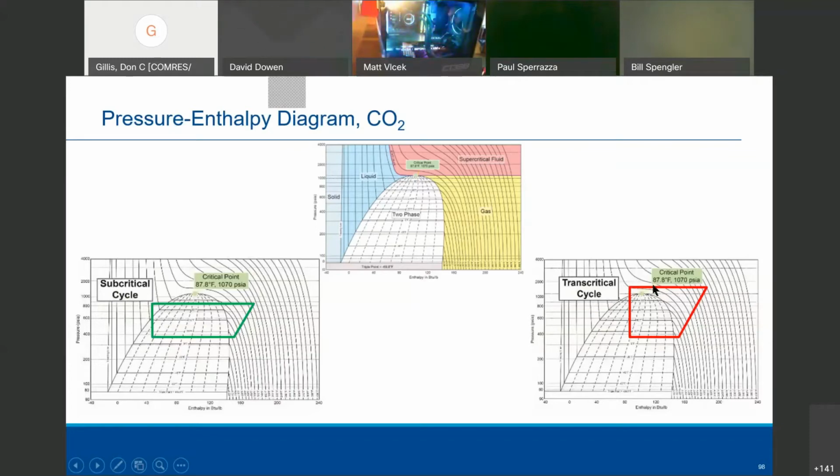When we get above that, you can notice how narrow our enthalpy chart gets over here in transcritical as it does in subcritical, okay? And then at the very top, I wanted to show you what that looks like in all three stages. And this is, as I know Andre mentioned earlier, in a lot of applications we'll purposely push that, even if it's in subcritical, in a lower temperature area to utilize that for reclaimed heat, reclaimed humidity, and for dehumidification and heat and water is the other thing I wanted to talk about.